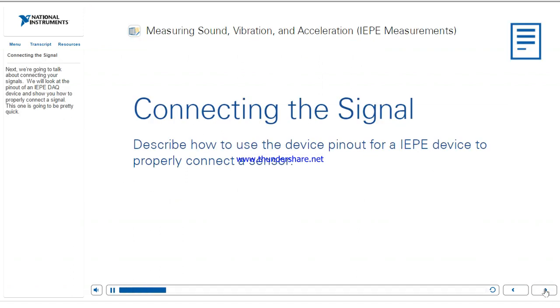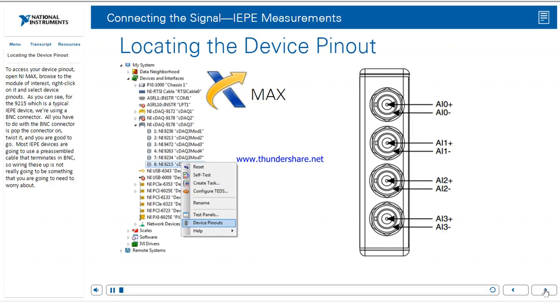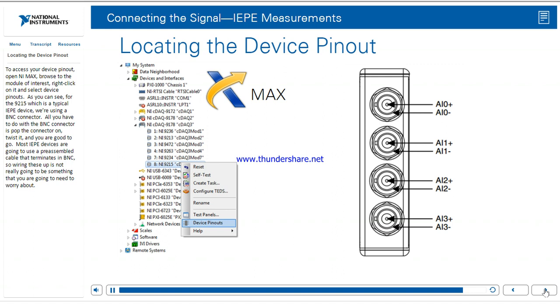Next, we're going to talk about connecting your signals — we'll look at the pinout of an IEPE DAQ device and show you how to properly connect a signal. To access your device pinout, open NI MAX, browse to the module of interest, right-click on it, and select Device Pinouts. For the 9234, which is a typical IEPE device, we're using a BNC connector. All you have to do with a BNC connector is pop it on, twist it, and you're good to go. Most IEPE devices are going to use a preassembled cable that terminates in BNC, so wiring these up is not really something you need to worry about.